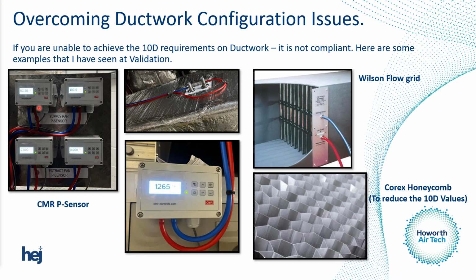And they also read a pressure as well, because everything that indicates a flow rate starts with a pressure. So you can see it's taking a velocity and static pressure. There's also a Wilson flow grid that works in a similar fashion, and if you're familiar with pitot traversing, you can see that it has these sensors across the duct, and it's reading a pressure and turning it into a velocity through some sort of sensor.